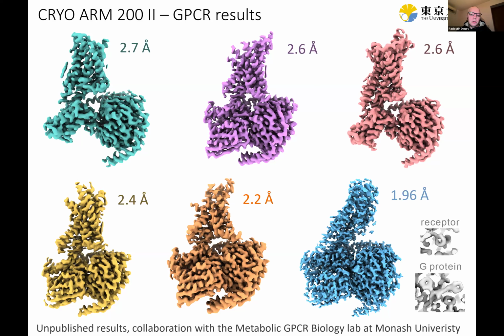And similar to what we got from the Krios G4, one of the GPCRs actually reached sub-2 angstrom resolution. I haven't checked the PDB recently, but a few months ago it was still only the third G protein-coupled receptor structure below 2 angstrom, the other two being done on the 300 kV Krios G4. So overall, the impression is that the results from the Cryo-200 are very similar in performance and outcome to the results from the Krios G4, a 300 kV machine.